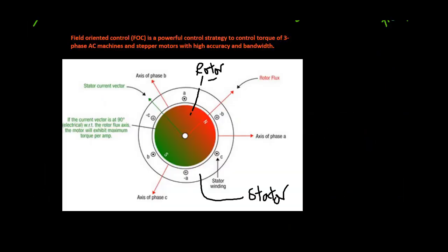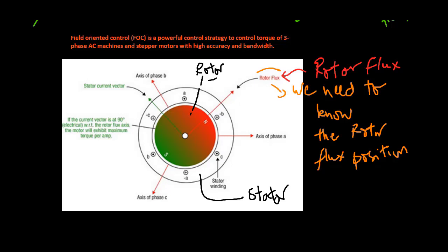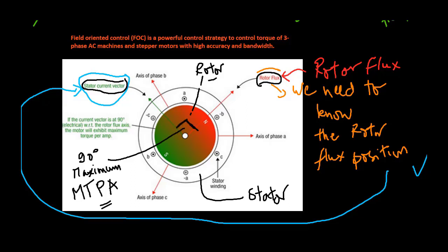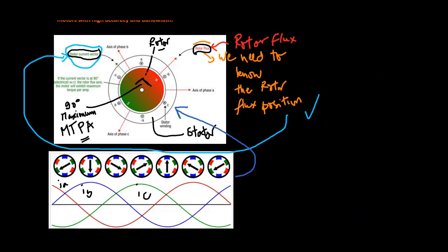The way that we do that is we first need to know the angle of the rotor flux, and there are different ways that we can get this. Once you know the angle of the rotor flux, you know exactly where you need to position your magnetic vector on the stator. We want that to be 90 degrees with respect to the rotor flux, because that gives us maximum torque per ampere. In real time as the motor is spinning, we apply three-phase currents to each one of the windings to generate a current vector 90 degrees with respect to the rotor flux.